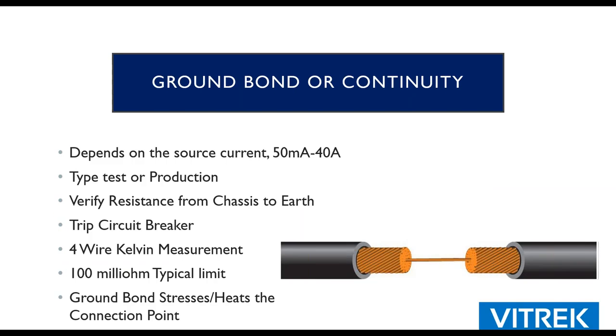All right, so another very common compliance test, there's basically two ways to do it. It's going to be a ground bond or a continuity test. Both of them are measuring the same thing. You're going to measure the resistance from your chassis to your earth ground pin. The reason you do this test is to verify that the chassis is properly bonded, and that if there was a failure, you could pass sufficient current through that earth ground lead to trip a circuit breaker.